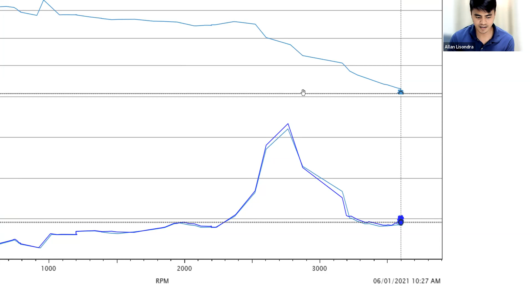Our manufacturer also gives us the specifications of our rotor. So before doing this, be familiar first with the specifications given by your manufacturer, because in the first stage, like during commissioning, this test was also conducted. You have to see the data in your documents based on the manufacturer design.